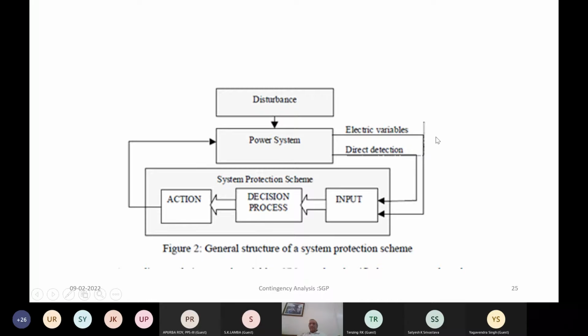This is the typical representation of a special protection scheme, where there is a disturbance which triggers power system certain parameters to change. There is a sensing of these parameters, or it could be direct detection of an event. For example, a tripping of certain tie lines of, for example, some HVDC corridor which is carrying say 1000 megawatt suddenly trips. So that tripping itself can detect and initiate a special protection scheme. Or because of tripping of one tie line and loss of that power flow, the power flow will get diverted and overload certain other lines. So you can take overloading of other line as the criteria and then trigger the special protection scheme. So that is the two ways of triggering the special protection scheme.